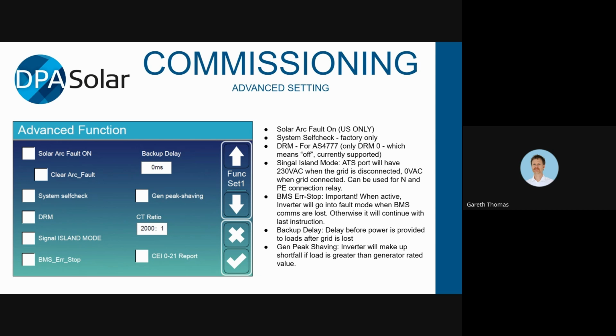Because I was looking at it, wondering if it could be used for an external bypass relay, so you could connect the input to the output like you can on a Selectronic or a Victron. But it seems like you might be able to do that, but there's no information from Noark saying that it 100% works that way. So you can't use it for that at the moment because it's not guaranteed. It just seems to work that way, but it's not guaranteed to only be on when the AC synchronization is complete.